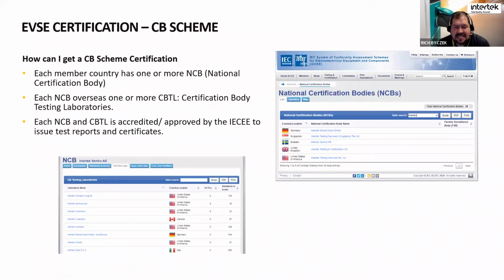So what does the CB scheme mean? It means you have essentially issued a passport for your product. One country's certification body has vouched that you've submitted samples, design criteria or design information for your product that meets the requirements within a specific IEC standard.